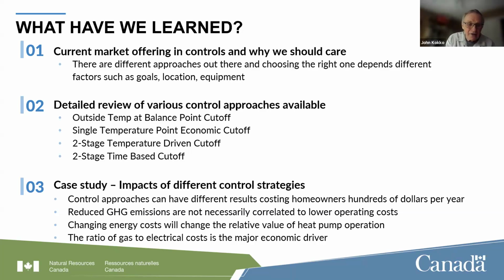The energy cost changes are going to have an impact on what the savings are if we're using heat pumps, and the ratio of gas to electricity costs is the major economic driver, as is the COP of the heat pump. So it's important to know what heat pump we're putting in.